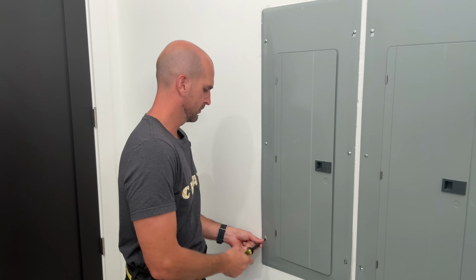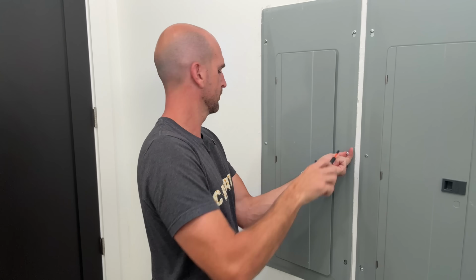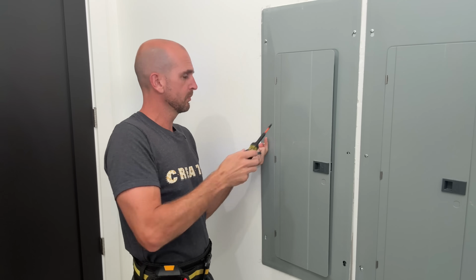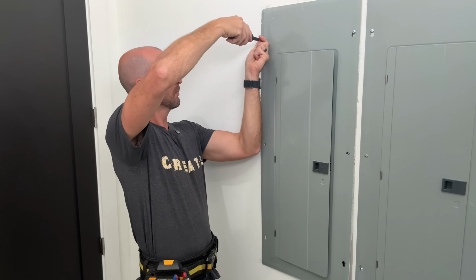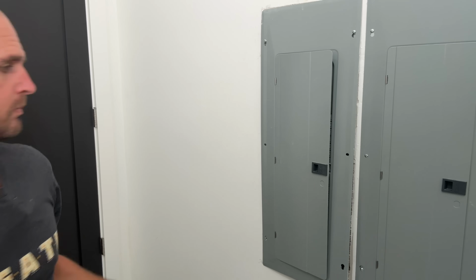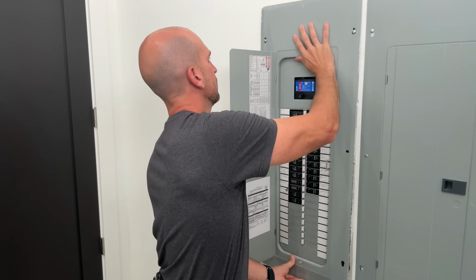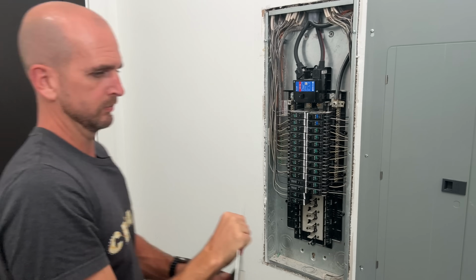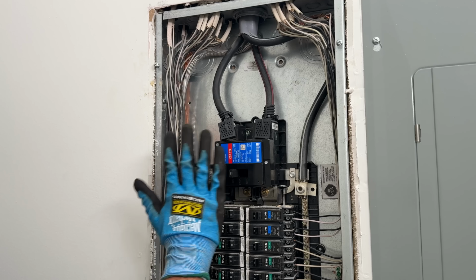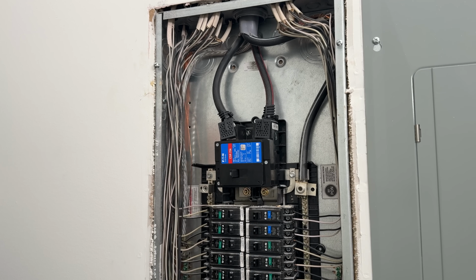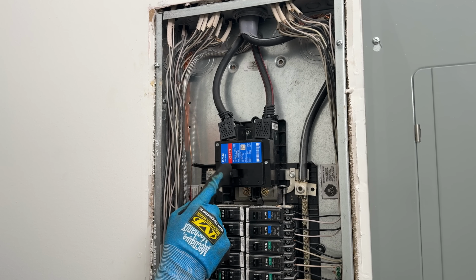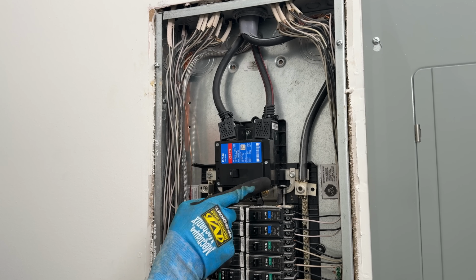Now, first up, when you remove the cover, take your time. Here I'm going to remove 4 of the screws and just loosen the top 2 so I can put the tool away and the other screws away. Have both hands to safely rock that away from the surface, ensuring it doesn't fall back into the panel. So now with the main panel open, and maybe even before you take that cover off, you want to turn your main disconnect in the off position.